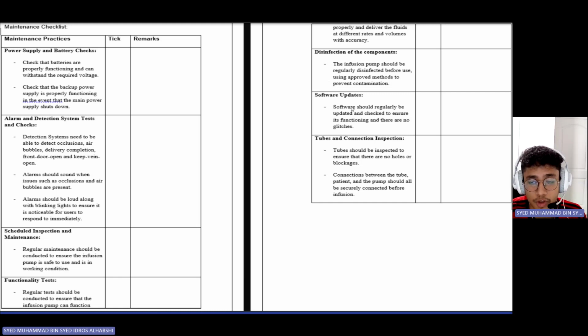Next, we have software updates. For the software updates, software should regularly be updated and checked to ensure it's functioning and there are no glitches. This is to ensure that when the users are setting the delivery rates and the limits, they are all accurate and does not overdose or underdose the patient. Lastly, we have tubes and connection inspection. Tubes should be inspected to ensure that there are no holes or blockages before infusing the patient. This is to ensure that all the required liquid is flowing to the patient at a steady rate and does not result in any complications for the patient.